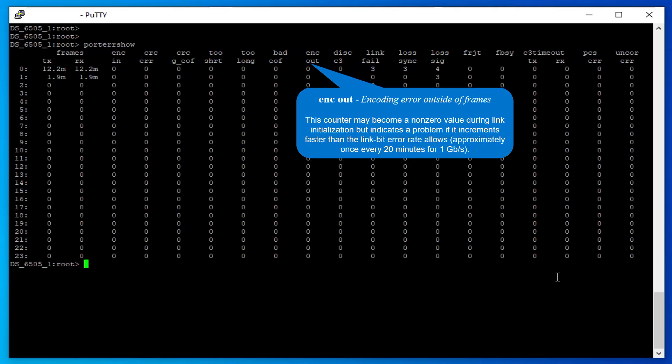Encoding Error Outside of Frames: This counter may become a non-zero value during link initialization but indicates a problem if it increments faster than the link bit error rate allows, approximately once every 20 minutes for 1 gigabit per second.